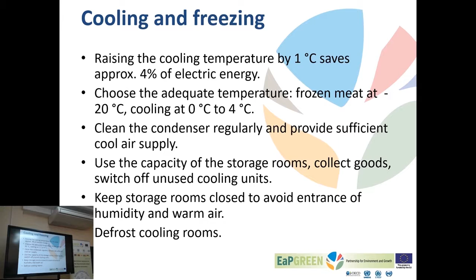Storage rooms, I know this is a tricky issue and interferes with the perception of operators for free flow, free movement, but the cold room should be closed as much as possible. We can do these calculations. We would underestimate how much additional cooling load we induce if we allow free flow of warm air into the cold storage. So whenever possible and whenever feasible, we should use at least these lamella curtains to separate the cold area from a warmer area, or use quick closing doors to separate these areas.